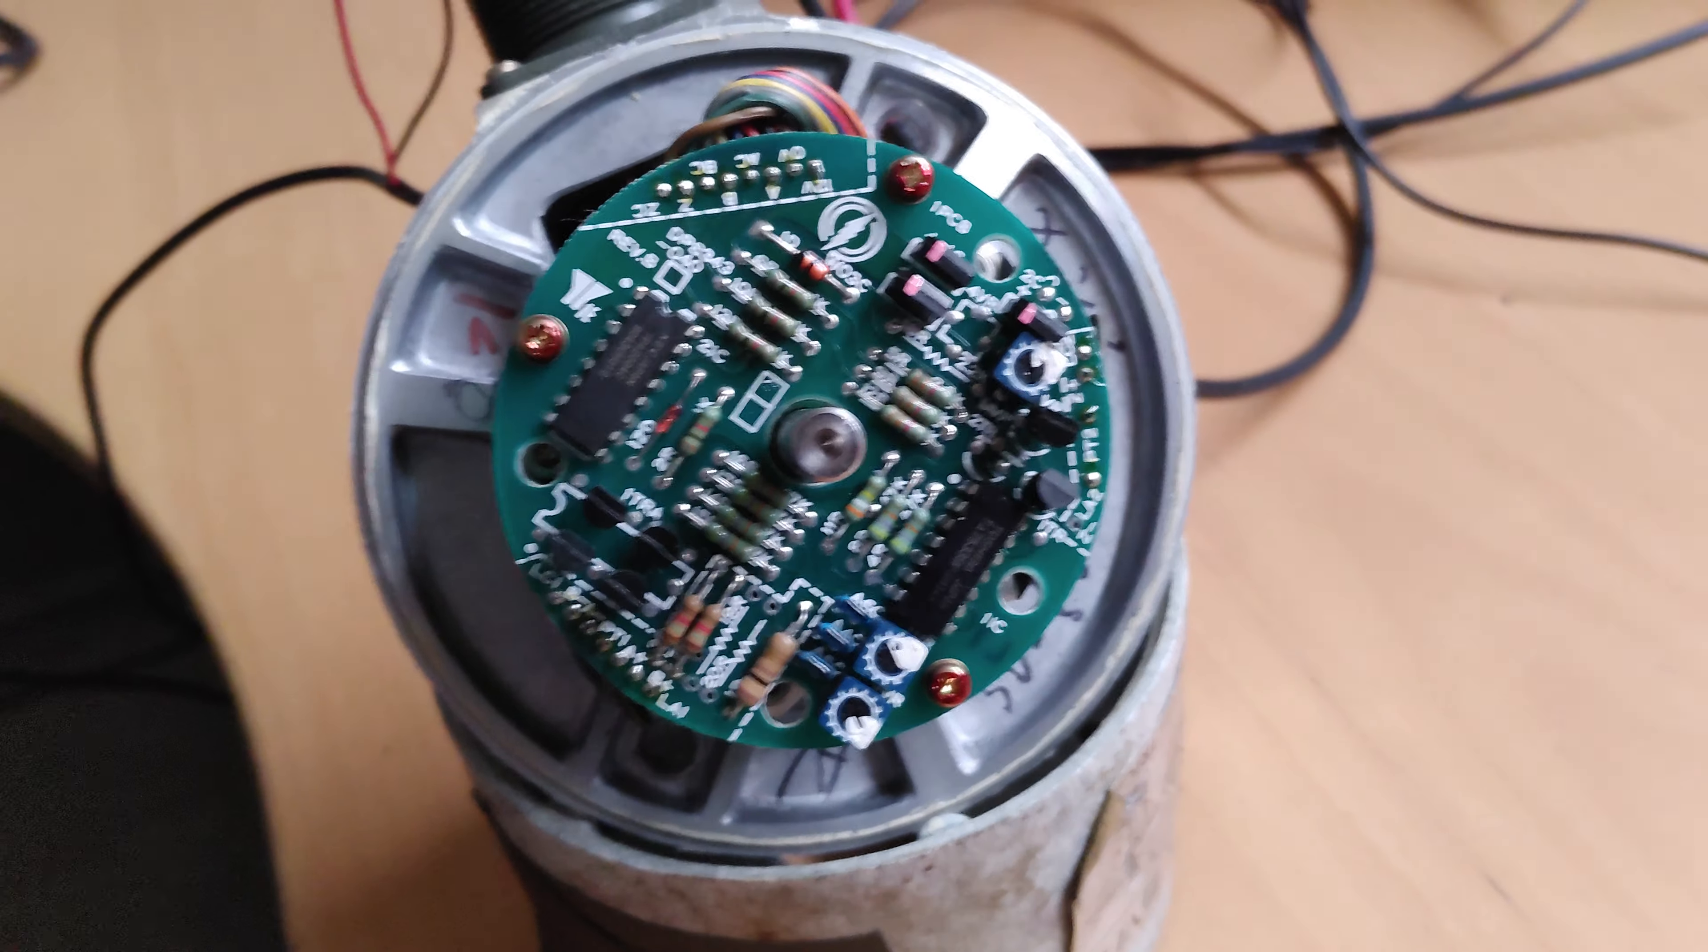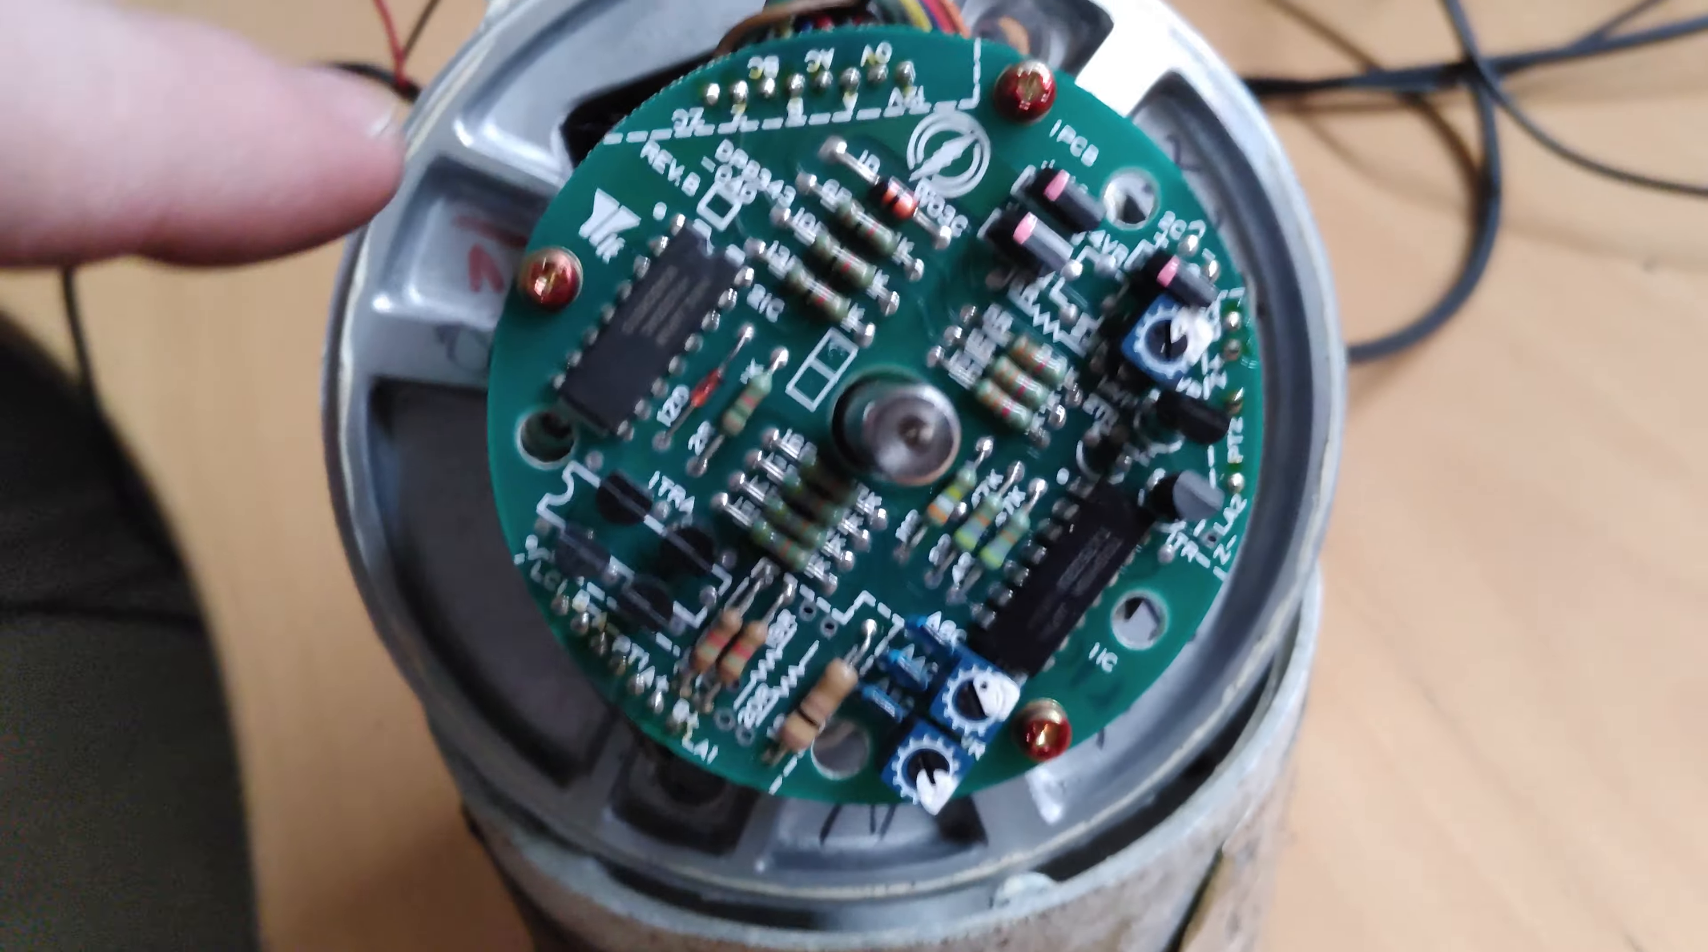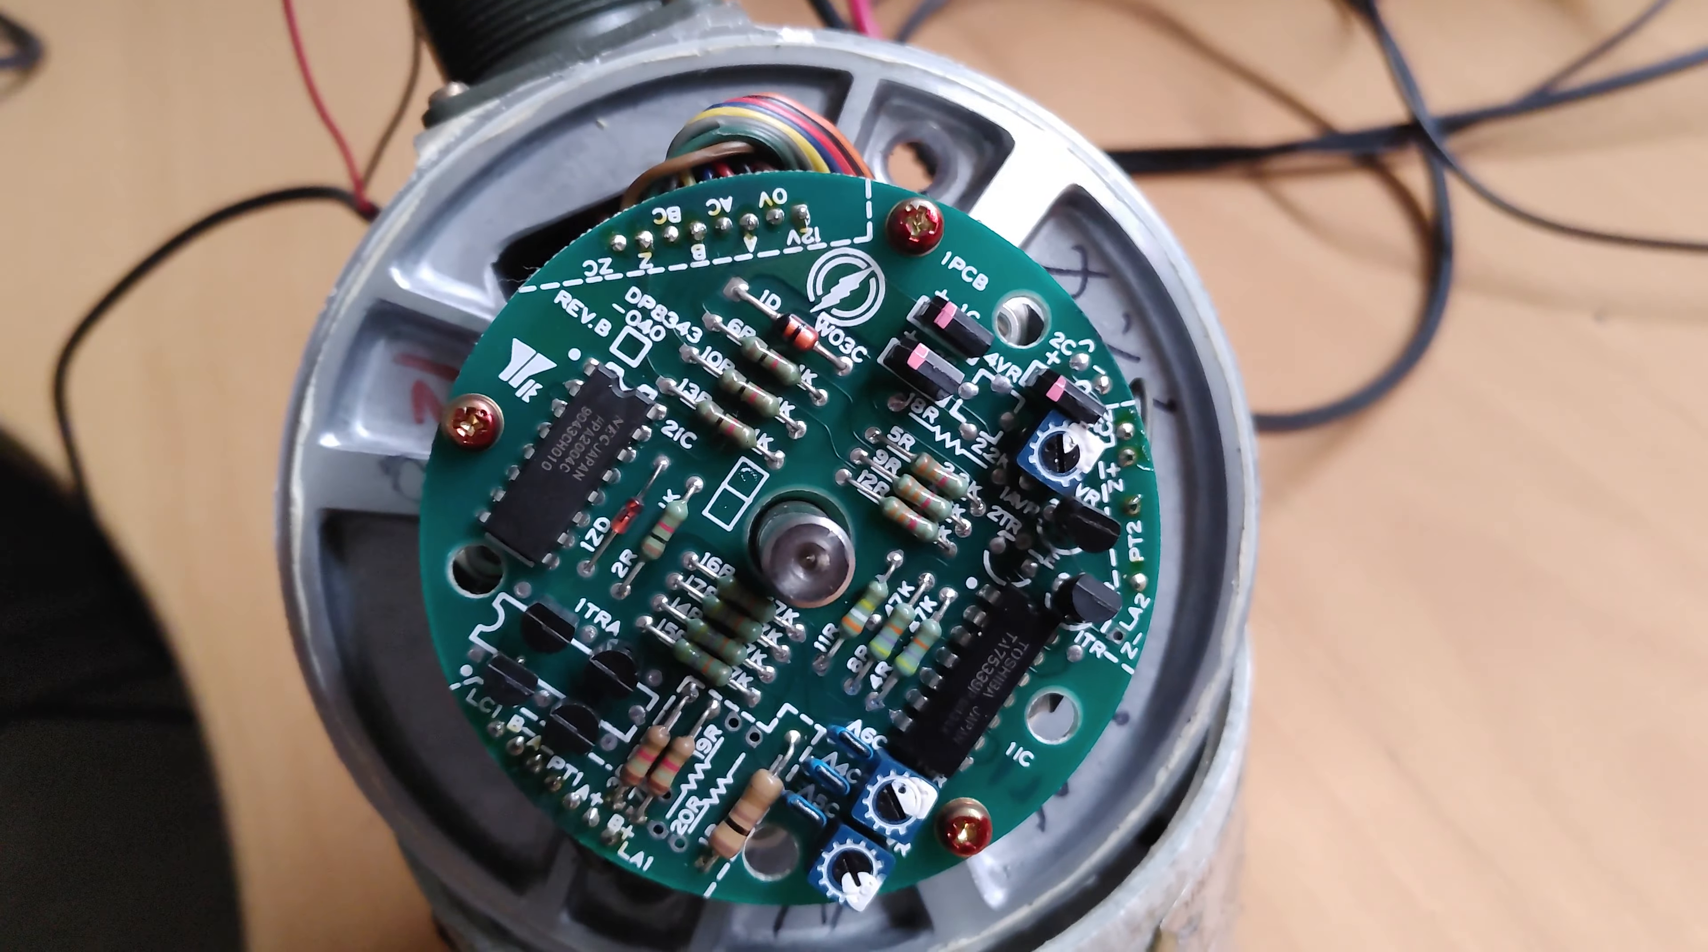It turned out on the Y-axis the Z channel was not sending the signal. So on an encoder you have an A, B, and Z. The A B is so many thousand pulses per revolution.